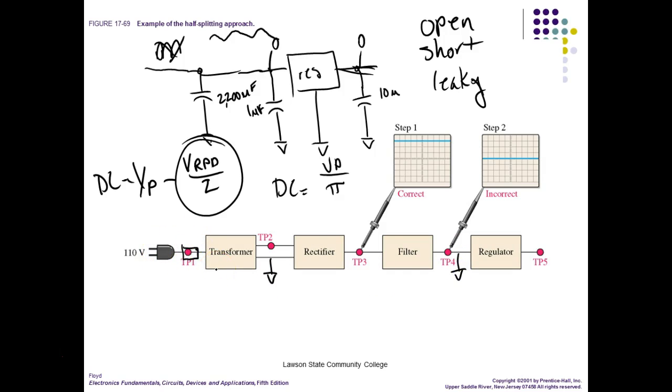How would I check a fuse with a voltmeter? With power on, because that's why we're troubleshooting right now. How would we do that? So what should I measure? Well, we could measure across it. We don't like to measure across things in the circuit. Why is that?